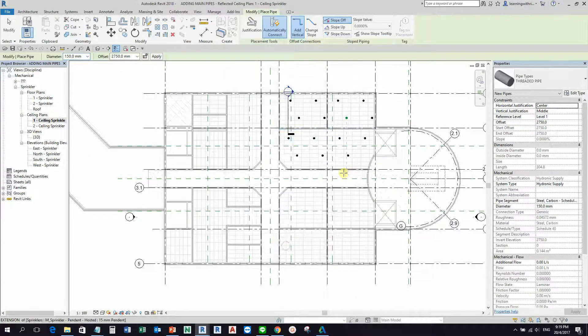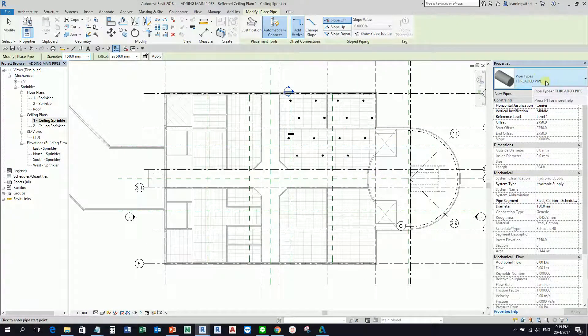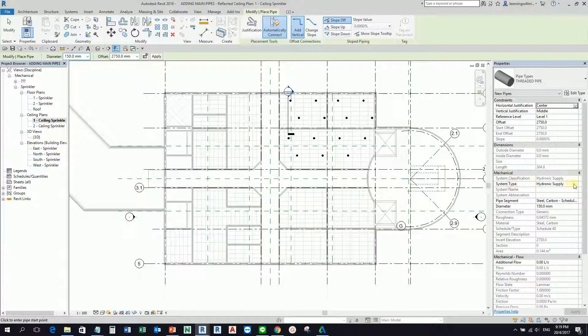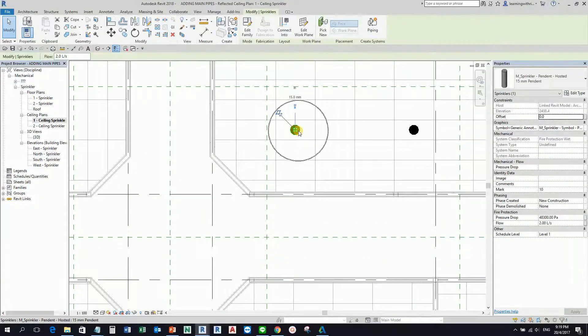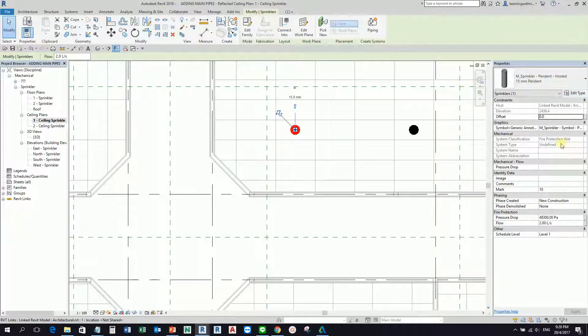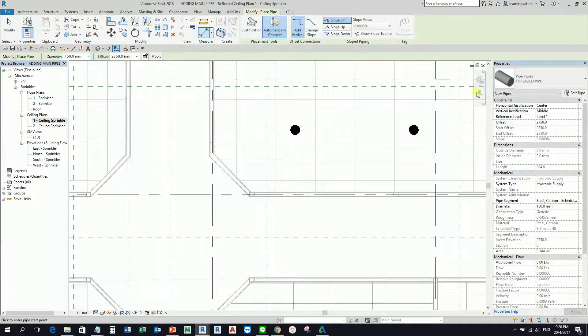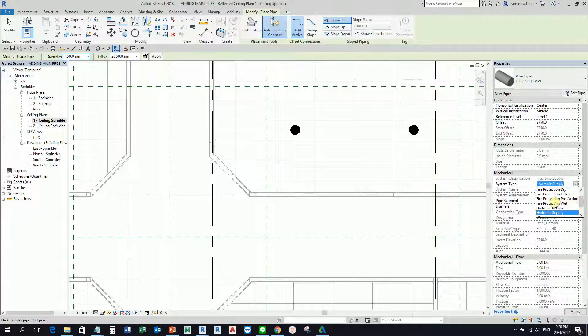I select OK and then OK again. Now to create the main pipe, aside from the pipe type make sure you also change the system type. Since we're on fire protection, let me select Modify for now and check this sprinkler — it's a wet system. So I go back and select pipe Threaded, system type Fire Protection Wet.